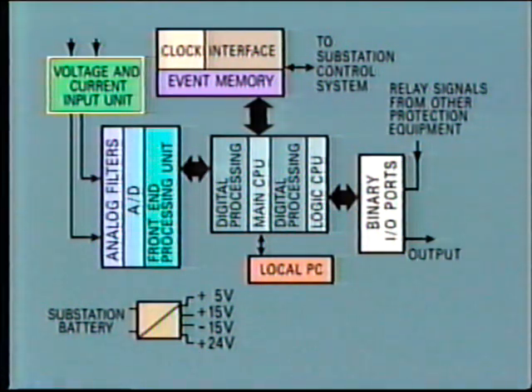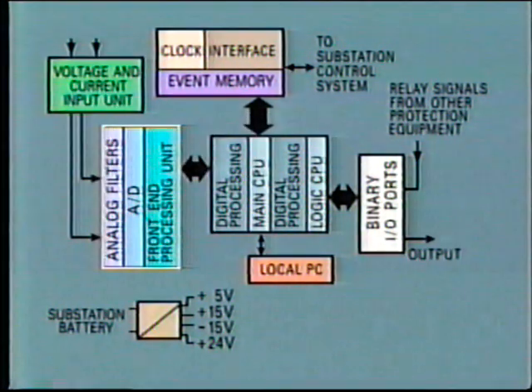Incoming current and voltage signals from the CTs and VTs are further reduced by transformers in the relay. The number of input circuits depends upon the specific relay, but quite often these may include current from each of the 3 phases, neutral current, and voltage for each of the 3 phases. As mentioned before, the A to D converter converts these incoming signals to suitable digital signals.